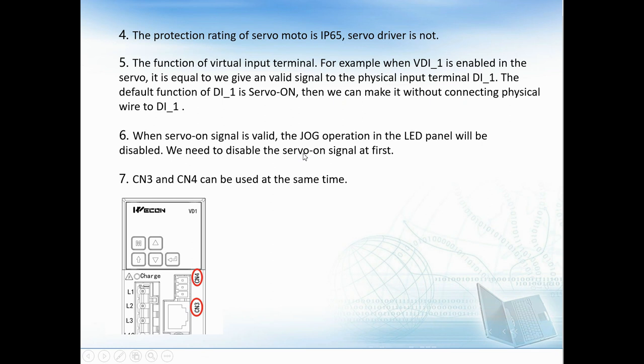Here are four more FAQ points. The protection rating of the servo motor is IP65, but the servo drive is not. Regarding virtual input terminals: when virtual digital input 1 is enabled in the servo, it is equivalent to giving a valid signal to physical input terminal DI1. The default function of DI1 is servo-on, so we can activate it without connecting a physical wire to DI1. When the servo-on signal is valid, the JOG operation from the LED panel is disabled — we need to disable the servo-on signal first. Finally, CN3 and CN4 can be used at the same time with no problem.